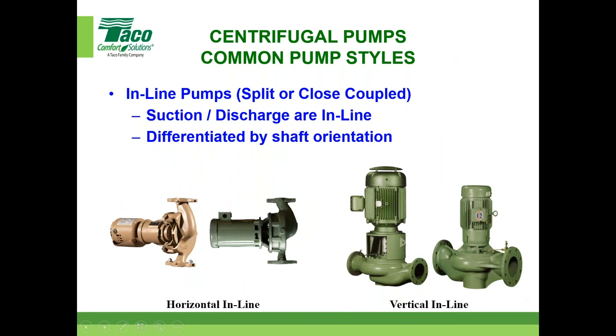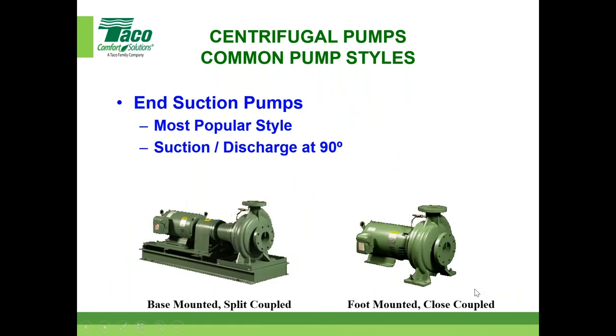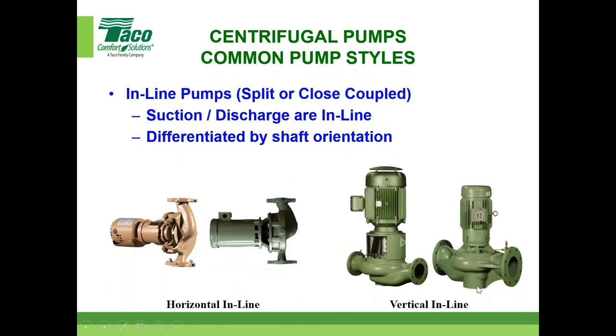If you read the IOM manuals that are attached, up to a certain horsepower, they're self-supporting. But once you get over, I think it's 20 horse, there are holes at the bottom of the casing or the wet end, and you can bolt a stand there. It's an option that you can buy the stand, but it can be supported from below. So it should be supported after a certain point of horsepower. Hopefully that answers the question. You got anything to add to that, Rich?